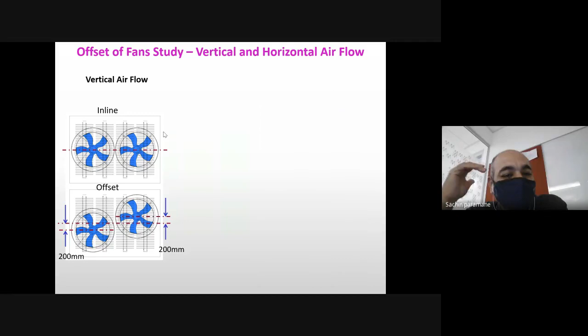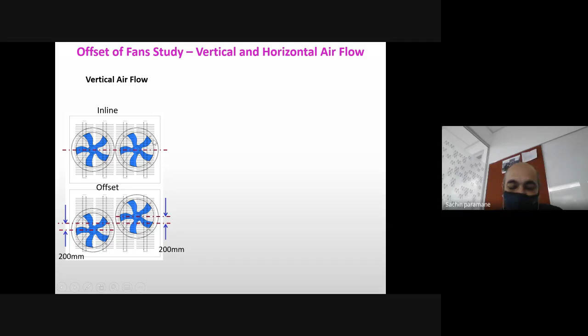Now, this earlier analysis was made for one particular type of fan. It is important to check that if we use a different type of fan, whether we are getting a similar result, or if we change the position of the mounting of the fan in a horizontal way, whether we will get any improvement. For that, again, two case studies were simulated by using a different type of fan. So this is a different type of fan, and here offset is 200 millimeter. This is inline and this is offset, and fan is blowing the air in the vertical direction. Similarly, fans are mounted on the sideways, and again fan offset was made as 150 mm, inline and offset.